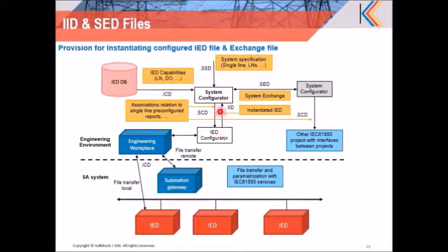So that in future projects, in other substations also, we can take that instantiated IED description file and use it to create an SED for other substation configurations. Rather than going with the global set, we can use the instantiated IED description and easily create an SED file out of that. This is point number one, the IED. So the SED creation becomes pretty easy, because we are importing an already configured vendor IED model and reusing it for every other project created. That is one of the key points.